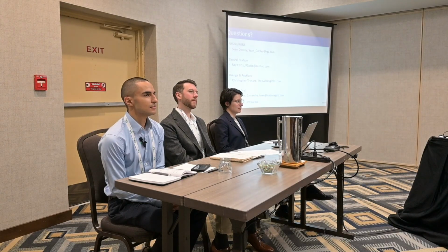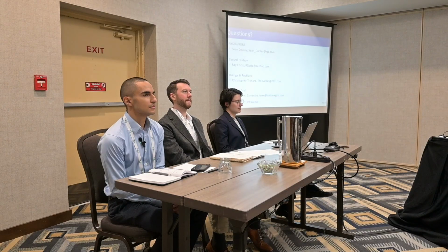Let's say you want to design at 0 but you actually design it at -5, size your equipment at -5, and submit at -5 - it's not going to qualify at -5. That's something we see often. You have to revise those loads, and it's potentially going to change how your equipment qualifies for the program.